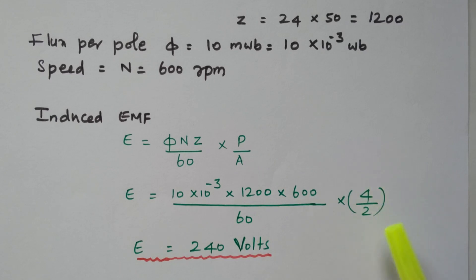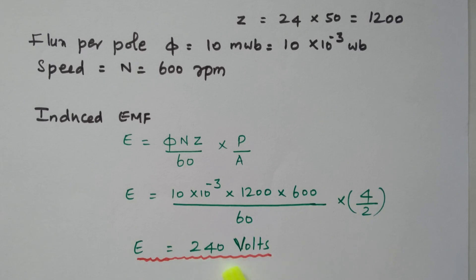Here, φ is flux, N is speed, Z is number of conductors, divided by 60, multiplied by P (number of poles) divided by A (number of parallel paths). Substituting: flux = 10 × 10⁻³, Z = 1200, N = 600 RPM, P = 4, A = 2 (wave winding). By simplifying, we get 240 volts. The EMF induced in the generator is 240 volts.